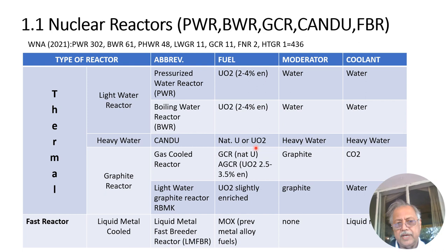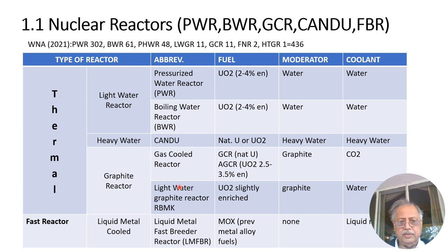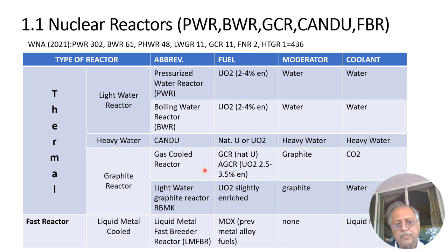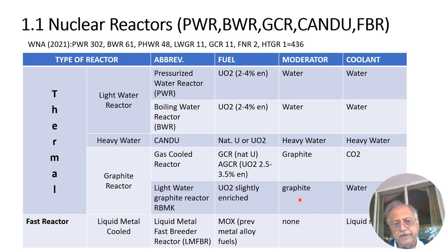Heavy water reactors originated in Canada — the CANDU, or Canadian Deuterium Uranium reactor — a natural uranium design using D2O heavy water as both moderator and coolant. Graphite reactors were historically first developed in the United Kingdom: the GCR Magnox reactors use graphite as moderator and carbon dioxide gas as coolant with natural uranium, later evolving to the advanced gas-cooled reactor with UO2 fuel enriched to 2.5–3.5%. Another graphite reactor is the Russian RBMK, which uses slightly enriched UO2 with graphite moderator but water coolant.